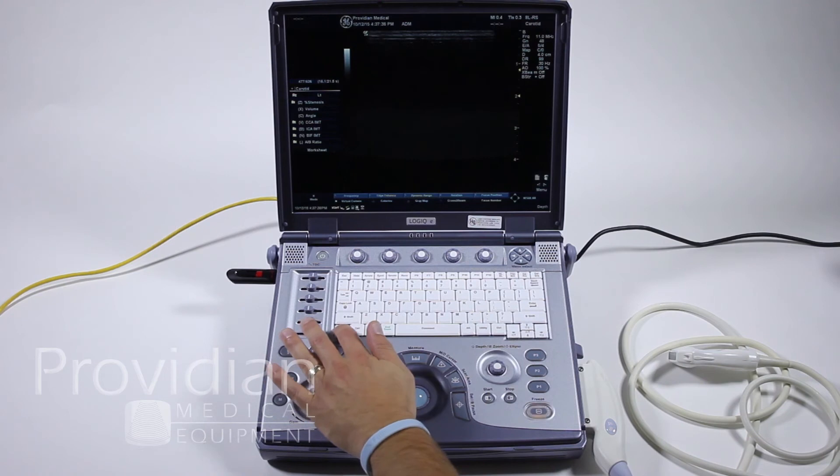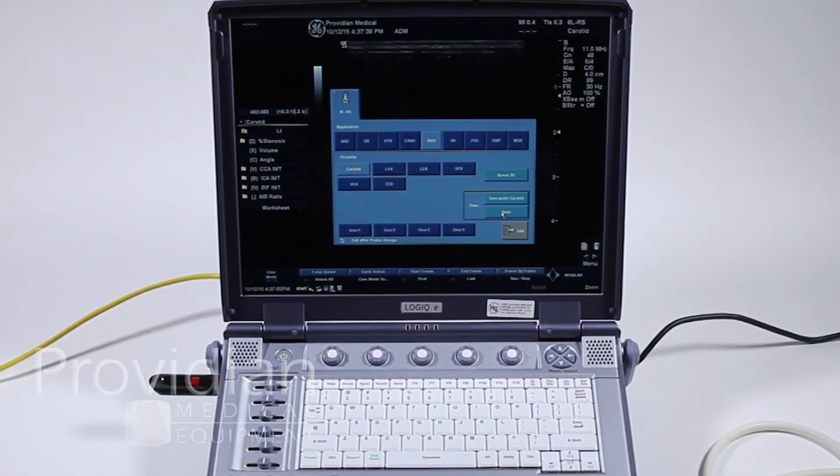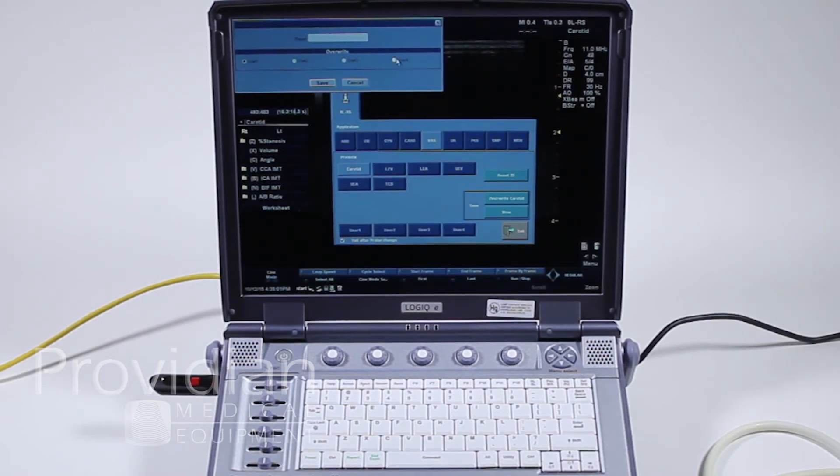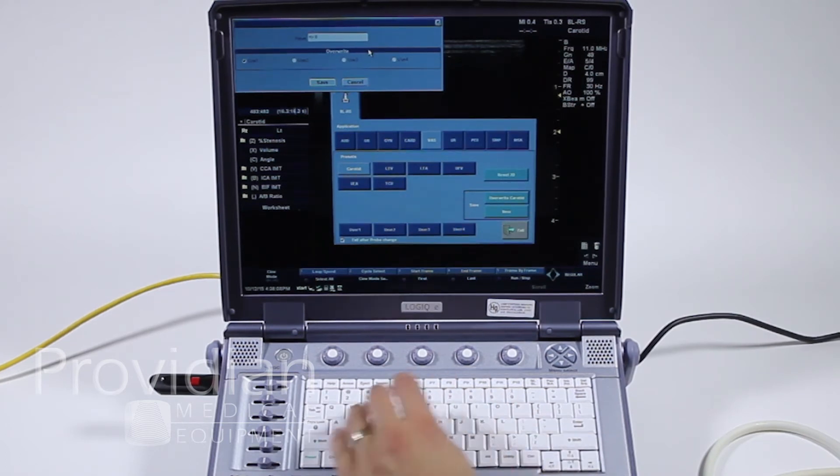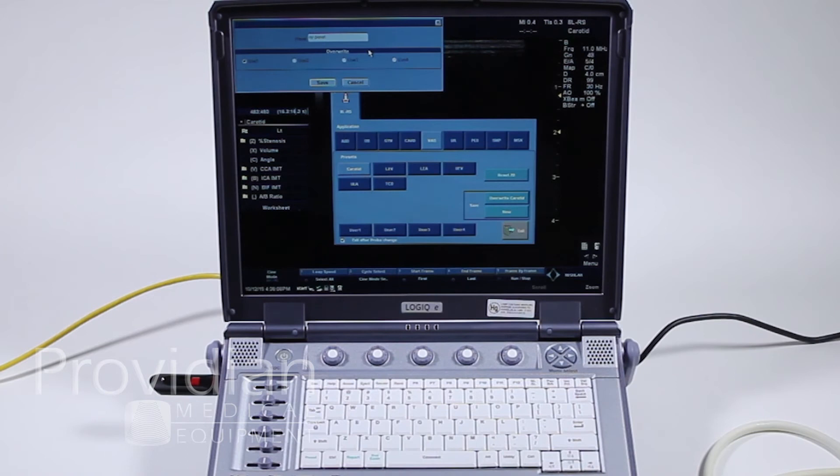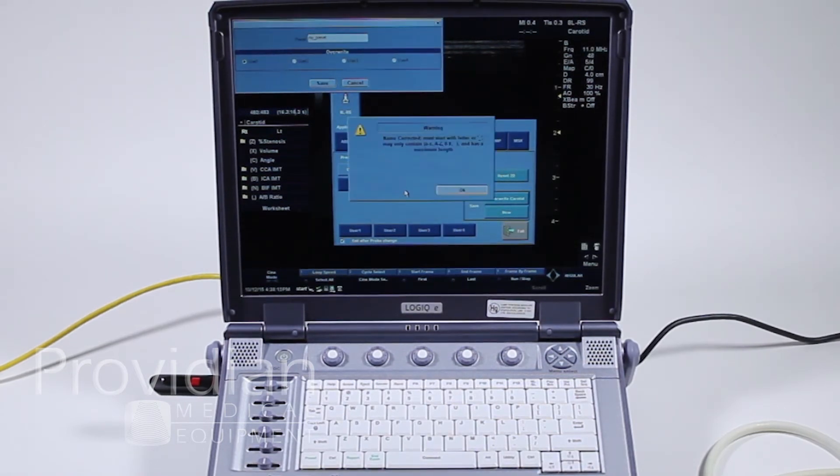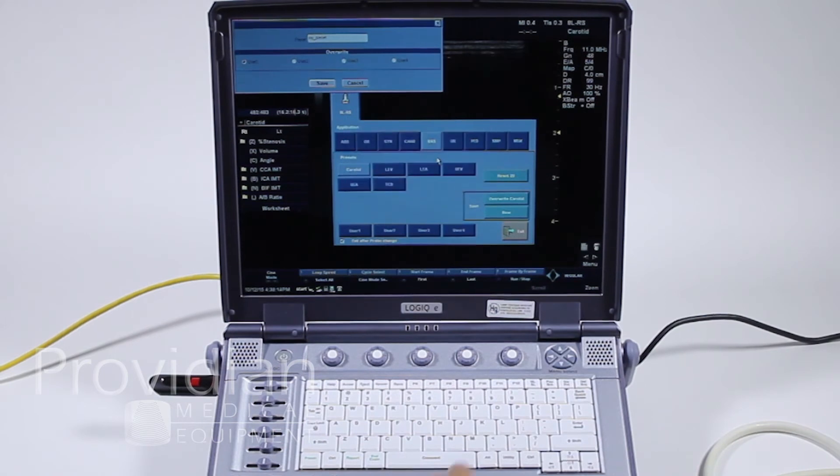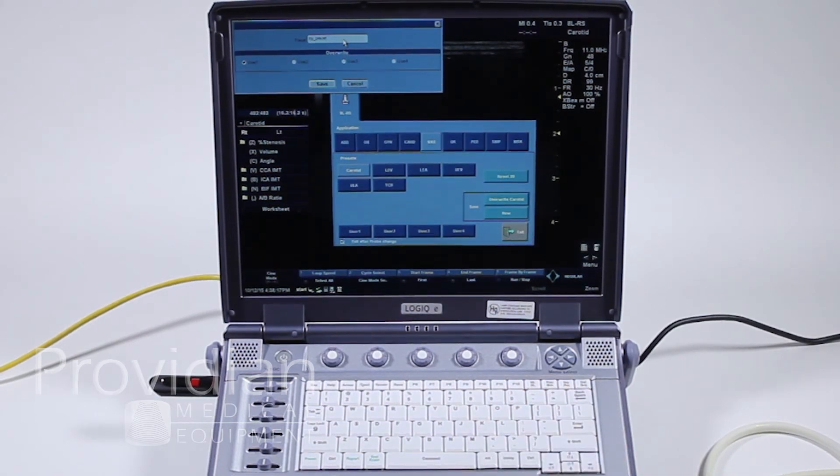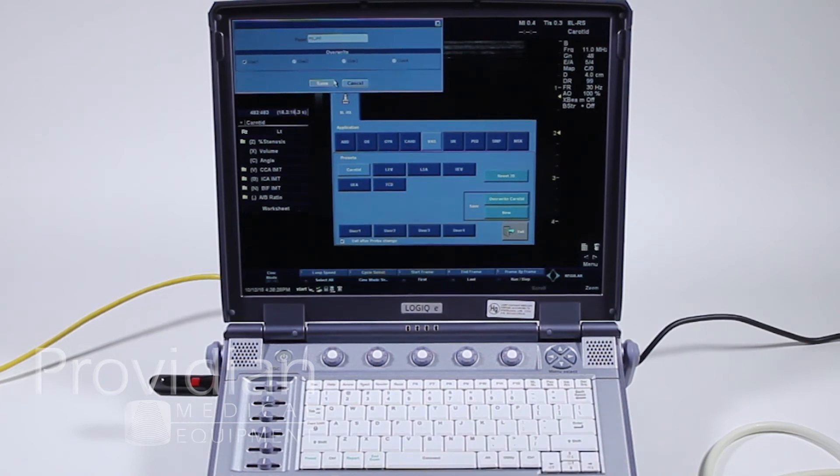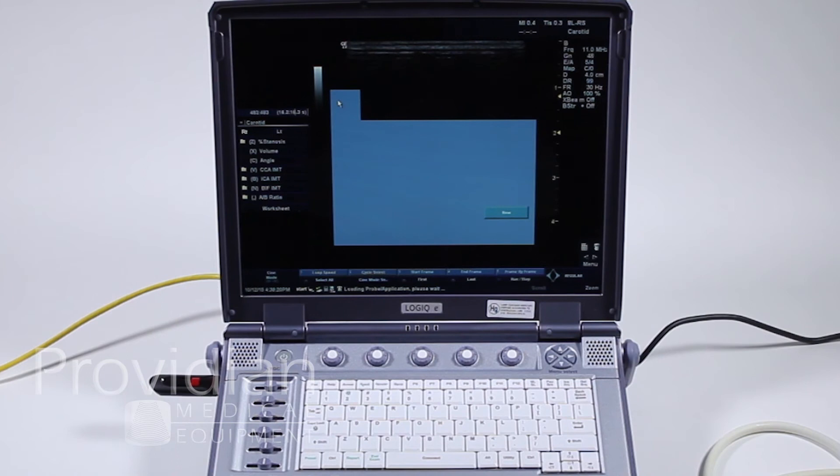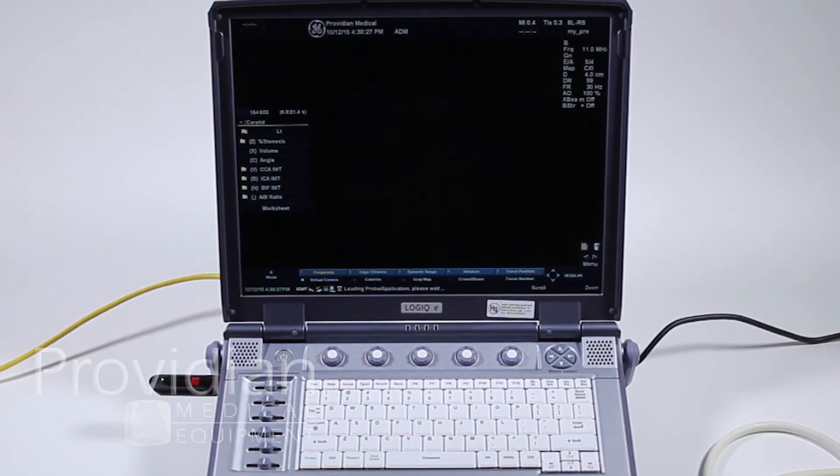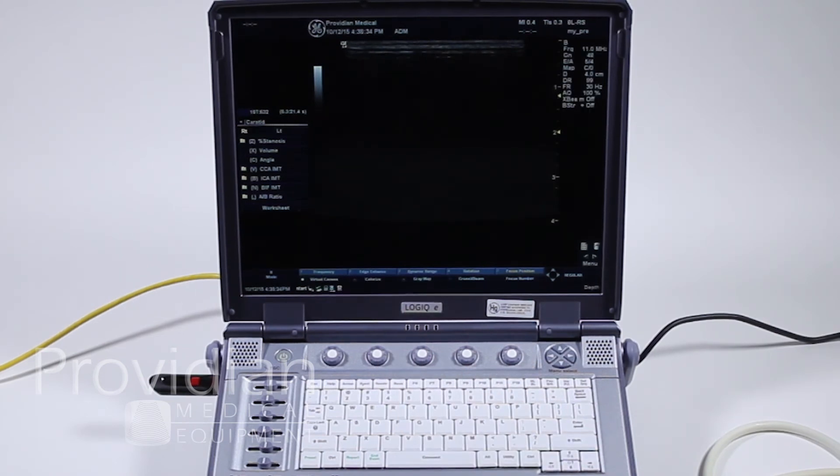I'll let that go away. And then I can just click preset. You can come over here and click new. And it's going to say, which one do you want? User one, user two, user three, or user four. And you can put in a name, my preset. Usually for multiple user situations, people will put their own names on it. I put too many characters in there. There is a limit as to how many characters. I have no idea what it is, but I'll just call it my pre. Click OK. And here it appears down here. So whenever I go into that vascular preset, all those changes I made will come up every single time. So I don't have to keep making those changes each time.